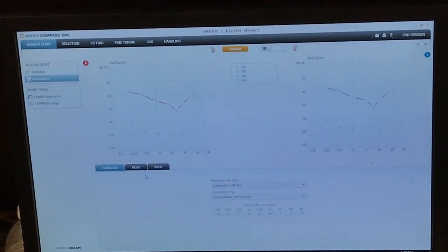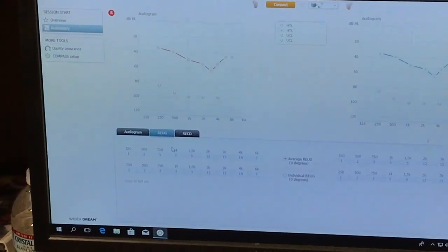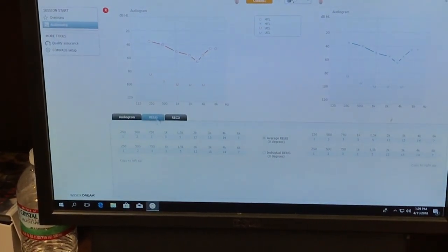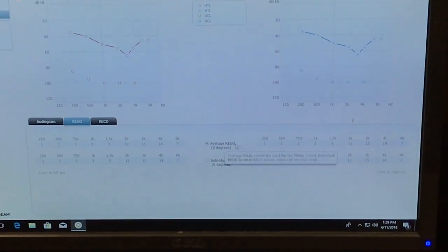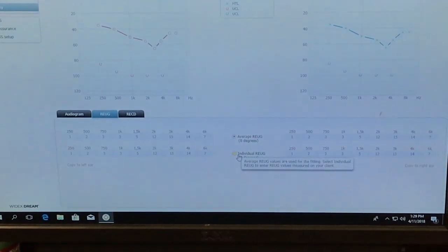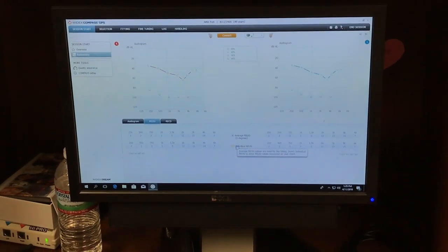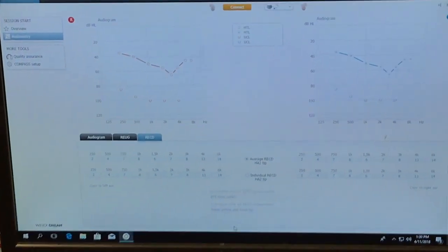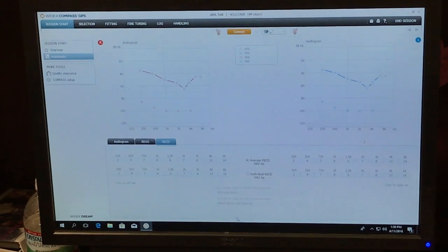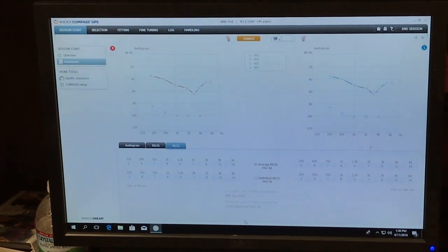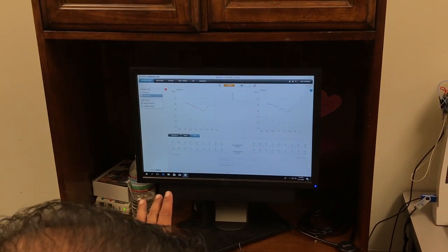But I want to show you while you're here, okay, is I can also put in what we call your real ear. We'll talk about real ear next time. Your real ear unaided gain. So this is your ear canal resonance. Right now it's average. Not everybody's going to be this. So I can put in your actual values and that'll tell me where the peak of your ear canal is, right? Quarter wave resonator. The other thing that I can do is put in what we call your RECD. That's the difference between the 2cc coupler and the person's ear canal. So now what I'm doing is adjusting the gain for the difference between the manufacturer's artificial ear and your ear. And for kids, you have to do this, okay? We're not ready to do this, but that's what we'll do eventually, okay?